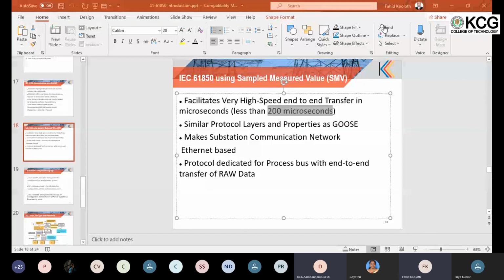So whatever is transmitted, we have an acknowledgement in TCP/IP for MMS. But GOOSE, since fast transfer is one of the key scenarios in GOOSE and sampled value, we cannot have the flexibility of an acknowledgement for each transmission. So what GOOSE recommends is best-case delivery, but in order to ensure delivery happens afterwards, the same GOOSE without any state change is transmitted again, for example after 4 milliseconds. Then after 8 milliseconds, that is doubling the time, the same GOOSE is transmitted again. Then after 16 milliseconds, the same GOOSE is transmitted again. Like this it keeps doubling until a new change comes and a new GOOSE is transmitted.